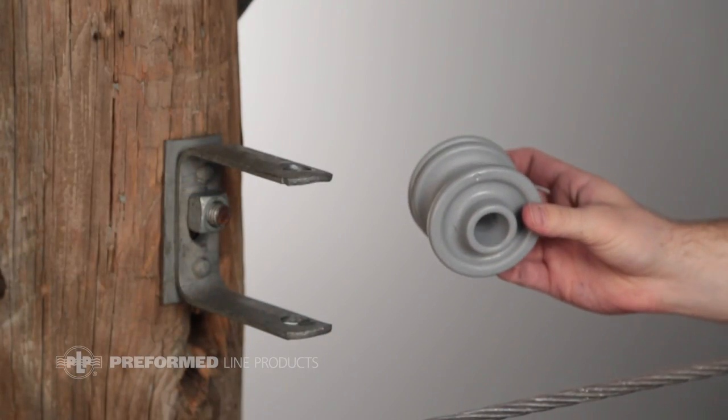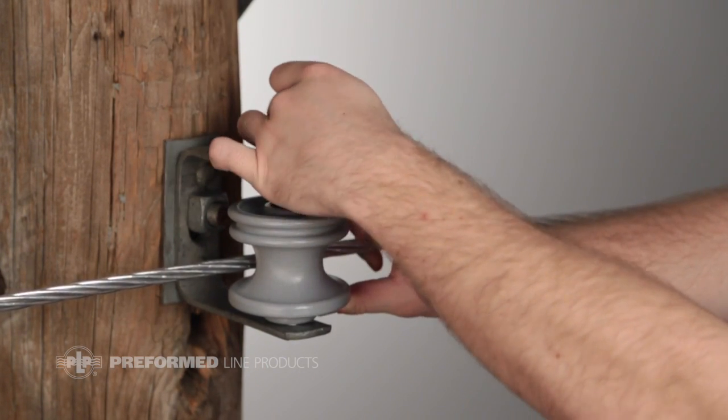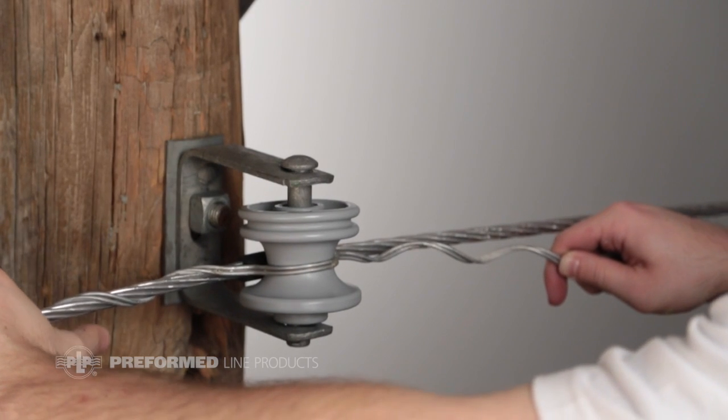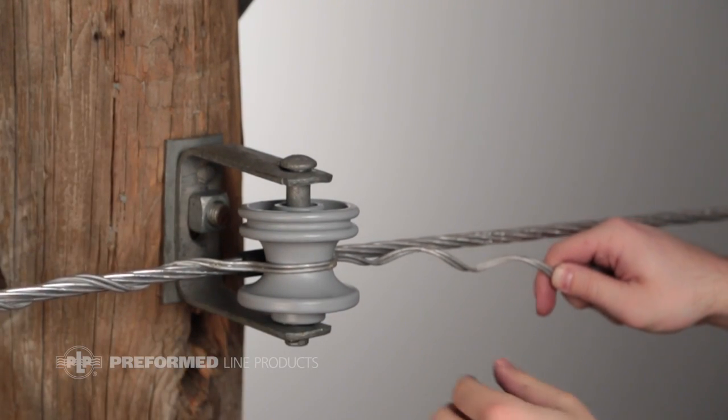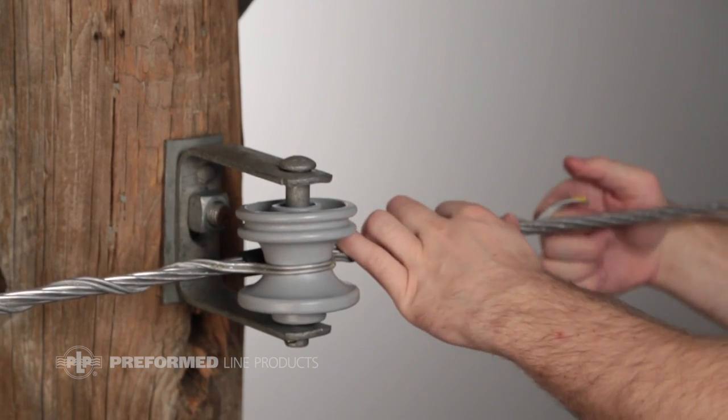It sounds like we offer a full line of insulators that meet most distribution primary applications. Yes, we do, but we didn't stop there. We now offer a polymer spool insulator that features a one and three-quarter inch neck diameter. It conforms to the ANSI 53-2 specification. It uses the same UV stabilized and lightweight material used in all our polymer insulators, making it ideal for use with bare, jacketed, or covered conductors. You can use PLP factory form spool ties on them, and they're suitable for use with any manufacturer's hardware that accepts the 53-2 porcelain spool insulator.